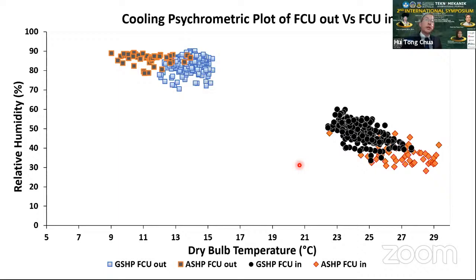So this is the cooling psychrometric plot of the fan coil unit outlet condition versus the fan coil unit inlet condition. Again, we have the ground source heat pump, with data in black, and the air source heat pump, with data in brown. You can see here that the householder in the property fitted with the air source heat pump prefers a warmer temperature, but very interestingly, the fan coil unit outlet condition for the air source heat pump is a lot colder than for the ground source heat pump.